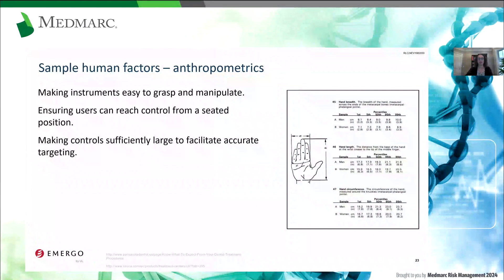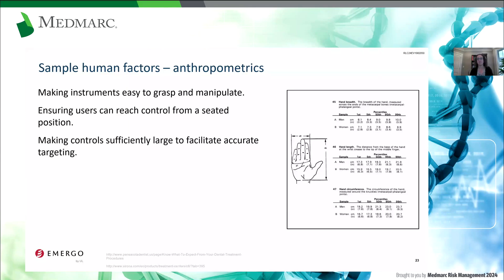We also think about size. If you're developing a surgical product, what are the hand sizes you're trying to accommodate? Are your users mostly males or females? Are they based in the U.S. or other parts of the world where people may have different sizing? This is really important when it comes to designing physical elements of the user interface — handles, handpieces, console components, drawers — making sure that physical controls are spaced out adequately so that someone can clearly target and actuate the control they intend to, as opposed to hitting a neighboring button.